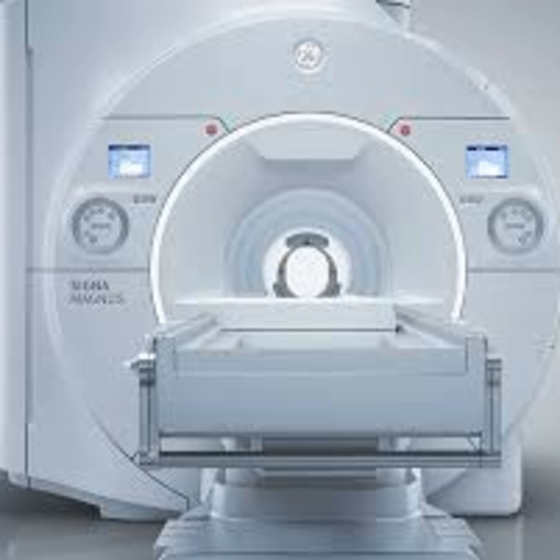Active shielding is even more sophisticated. Modern scanners include secondary sets of electromagnetic coils located outside the primary magnet. These coils carry current in the opposite direction, creating a counter field that effectively cancels out the primary magnetic field everywhere except inside the bore of the machine. This ensures the powerful force is concentrated precisely where the patient is positioned, while the rest of the hospital remains a magnet-free zone.